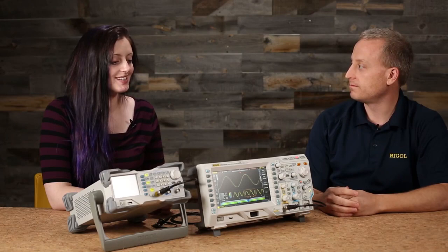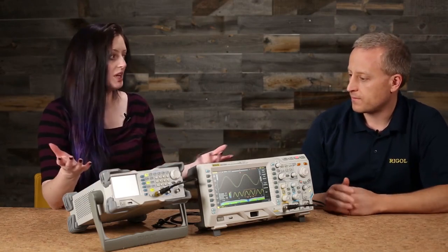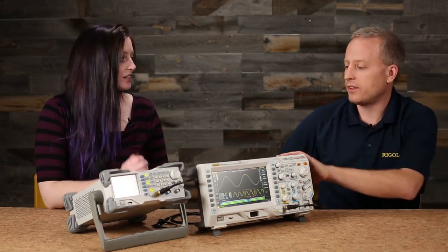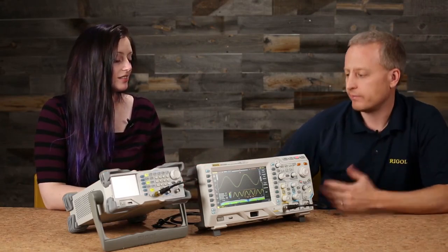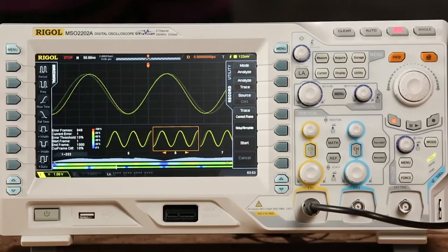That's really interesting. Okay, you captured 1,000 frames. You can do a lot more than that, can't you? Yeah, this instrument can capture tens of thousands, at least 32,000 frames in its normal mode. It all depends on the memory depth you want and the time base. Yeah, and that is something I see you guys really strong in. A lot of memory in these devices.